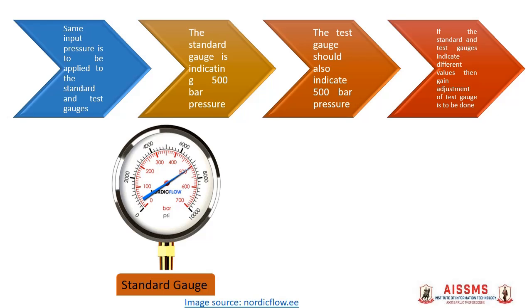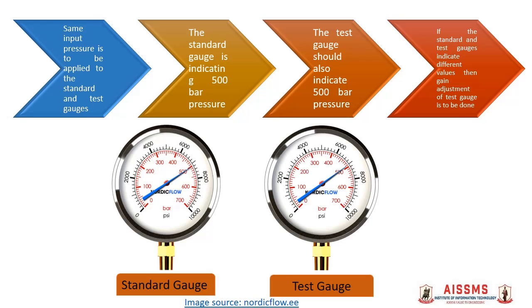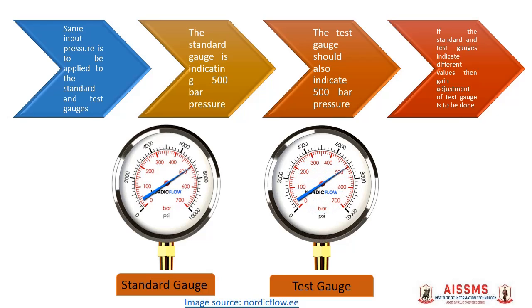It is expected that the test gauge should also indicate 500 bar pressure. If the standard and test gauges indicate different values, we need to adjust the gain of the test gauge so that it indicates the same reading as that of the standard gauge.